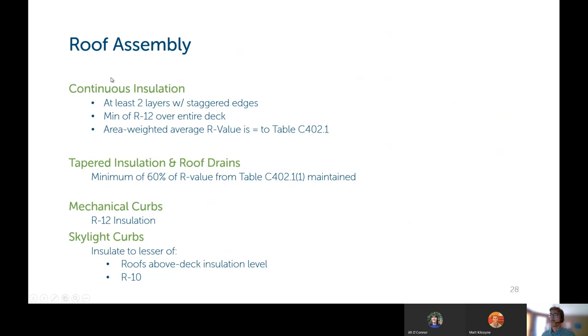For the roof assembly, when you are using continuous insulation, you must use at least two layers of insulation board with staggered edges. You must have a minimum of R12 over the entire deck. And the area weighted average R value must be equal to what was listed in those previous tables. So if you need to go below the required value in some areas, you need to go above that in others to make the area weighted average equal to the requirements in the table.